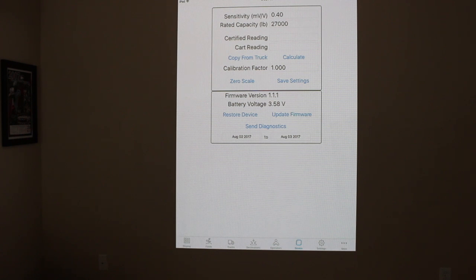So once again, it's taking the actual weight divided by the incorrect weight times the rated capacity at that point in time. So that rated capacity will change, and that number, if you're doing several calibrations, will not be 27,000 each time. So that's not a quantitative figure, it's not X. It will be a changing figure if you're getting it closer. And then when you get within 1% or so, if you come in, say 1% high, 1% low, then you're probably right in that target range, basically.